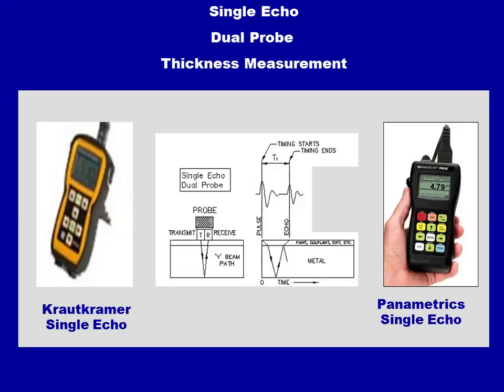There are two inherent problems with this technique. If you have any coatings, paint, or epoxies on the steel, the velocity of sound in that paint is probably 2 to 3 times slower than in the steel. We've calibrated the instrument for the velocity of sound of steel if you're measuring the steel wall, and you can only calibrate these instruments to one velocity of sound.